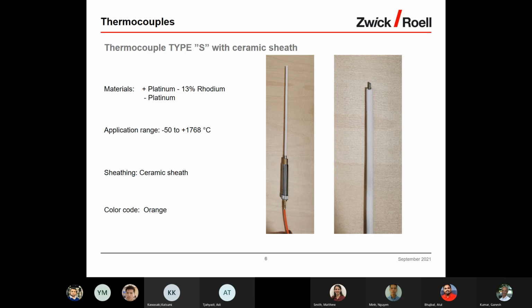Next thermocouple, type S with ceramic sheath. The material is also, on the plus side, platinum and 13% rhodium, on the minus side, platinum. Application range -50 to +1768 degrees Celsius. The sheathing is ceramic sheath. The color code is also orange.